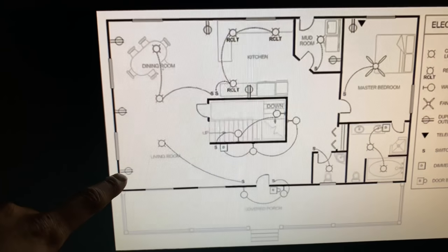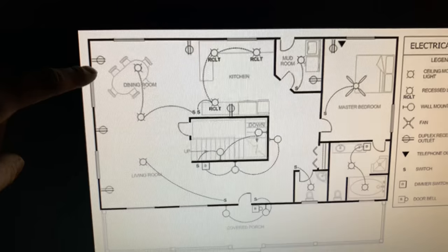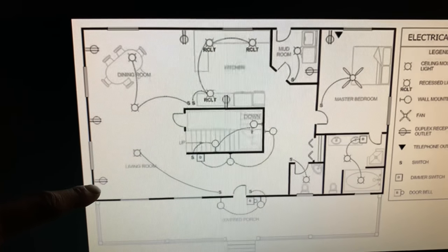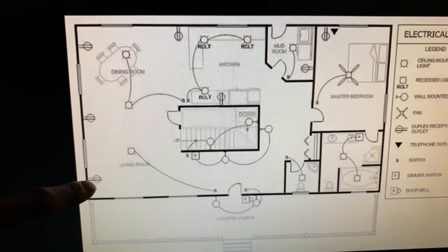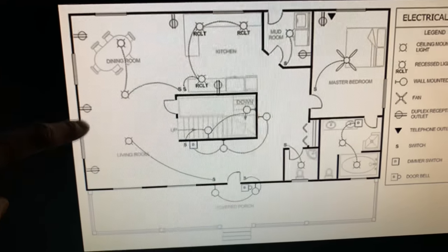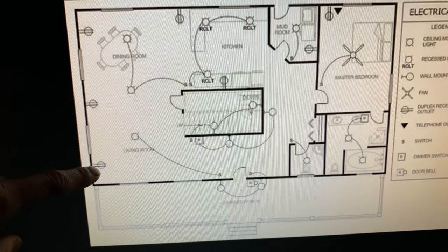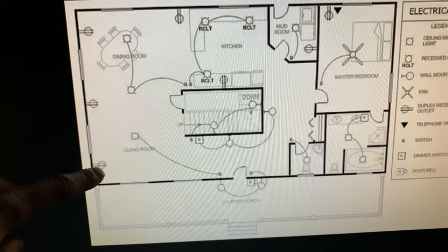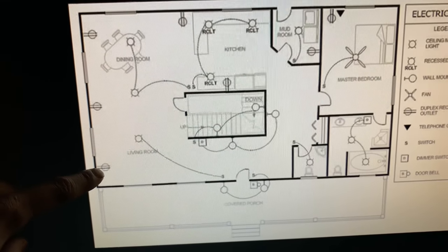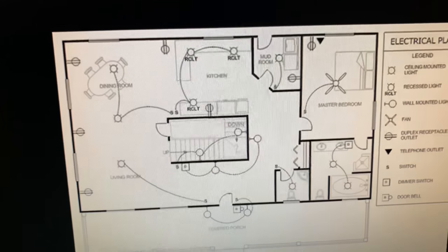You've got your plugs here. Like I was saying, the plugs change direction depending on which wall they're on. Let's just make up a scenario that this is one circuit. So this plug goes to here. You need a wire from here to here, from here to here, here to here. So each box will have two wires, basically. Say the home run starts here, that goes to the panel, and then you daisy chain from this plug to this plug to this plug to this plug, so each box will have two wires.